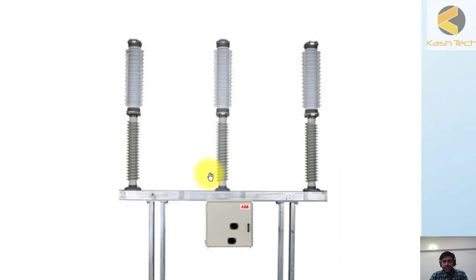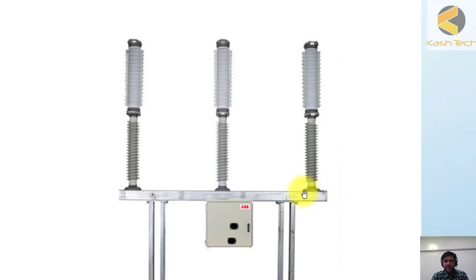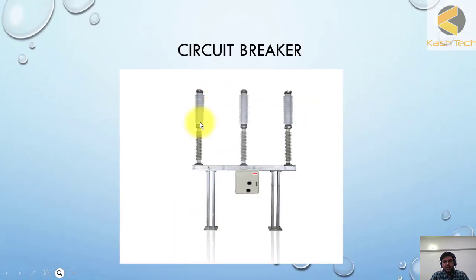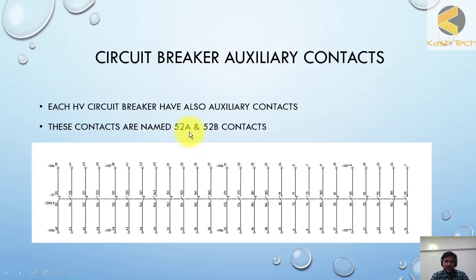There are two types of breakers: one where a common mechanism drives all three poles to interrupt the current — called three-pole operated breakers — and another where each pole has its own mechanism to open, called single-pole operated breakers. At extra high voltages, single-pole operation is normally used at 220, 380, or 500 kV level, whereas at 132 kV and below, either single-pole or three-pole mechanism (a single mechanism driving all three poles) is used. Each circuit breaker when it operates has its own auxiliary contacts.